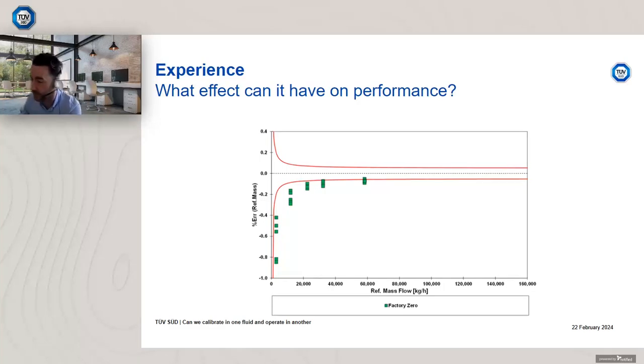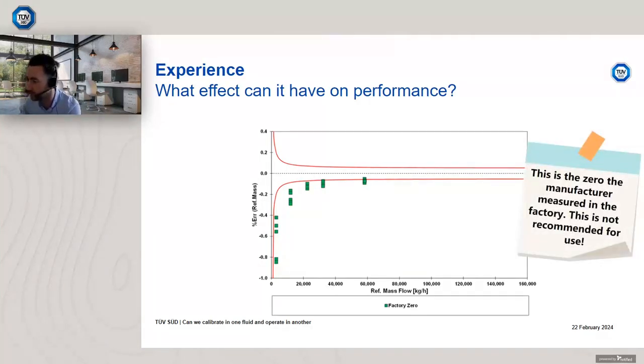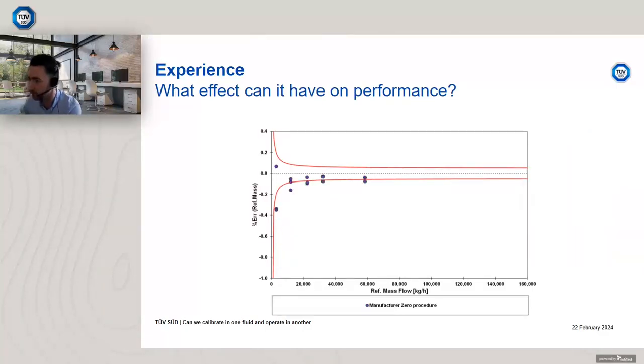Now this is as expected. I wouldn't recommend that you do this. So this is the zero the manufacturer measured in their factory. It's not recommended for use. You should always check and verify your zero in situ, and if it needs to be re-zeroed, you follow the zero setting procedure from that manufacturer or NEL's procedure.